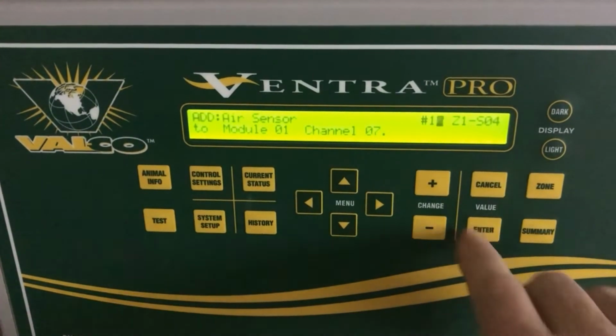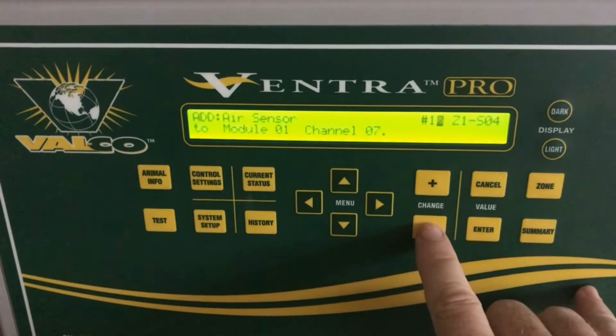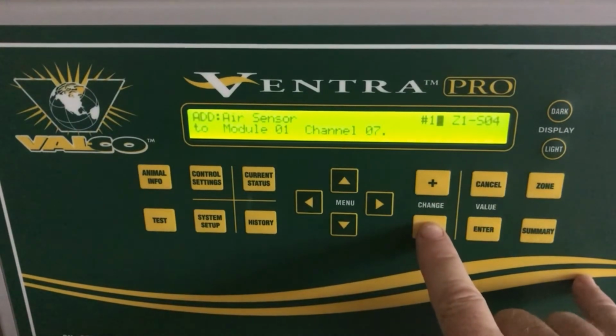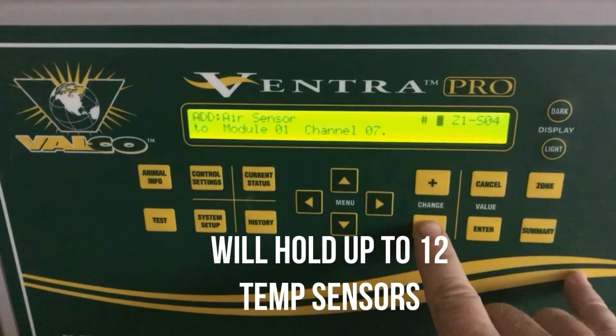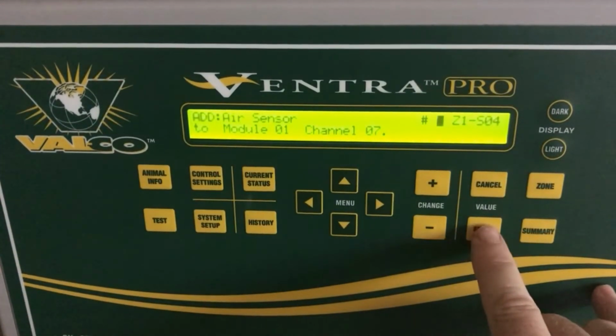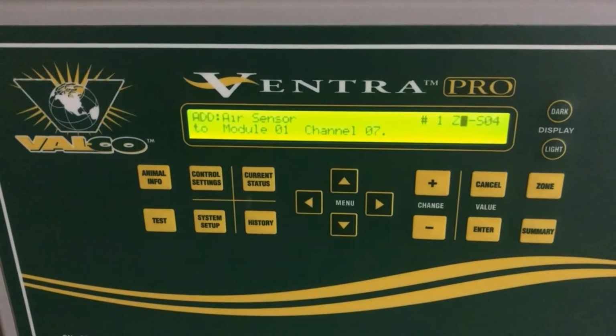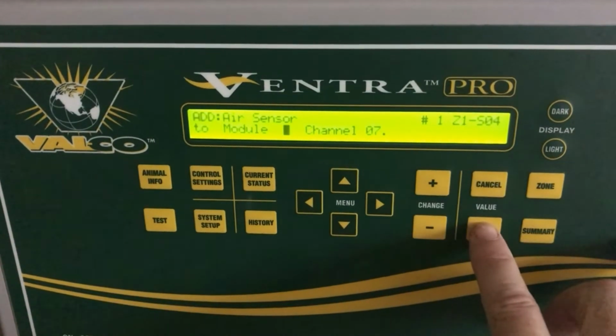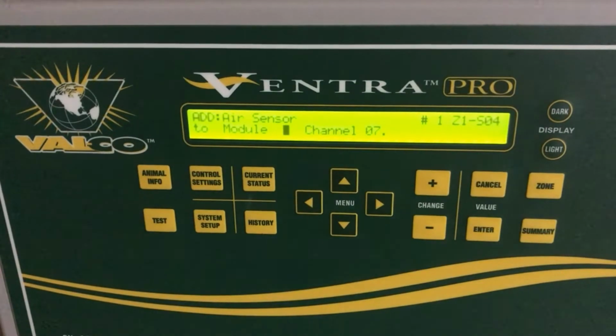So we press Enter. Then we choose the number sensor that this is. The Ventra Pro will hold up to 12 temperature sensors. And in this case, this is our very first temperature sensor, so I'm going to choose number 1, press Enter, and then I choose the zone which this temperature sensor will be programmed to. I only have one zone programmed, so I will leave it on Z1. Press Enter, then I choose the module. You will always choose module 1 unless you have an expansion station that you are programming into your system.